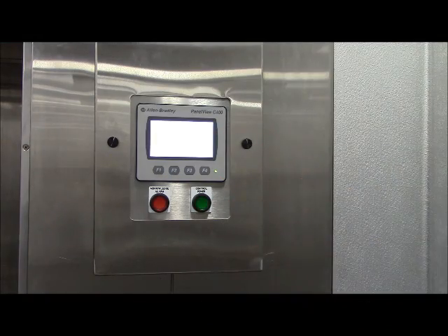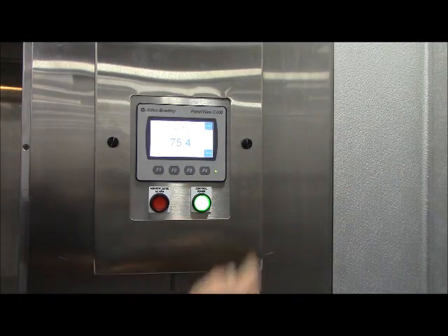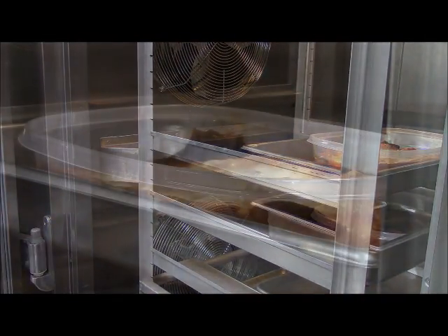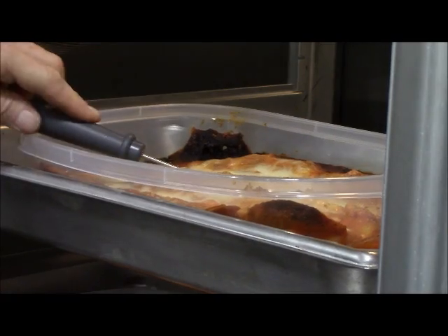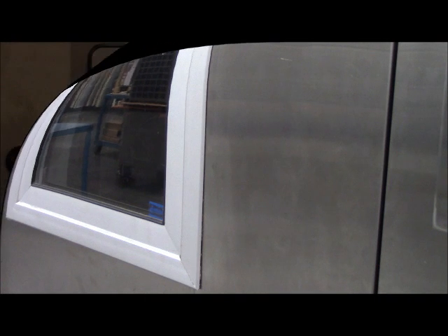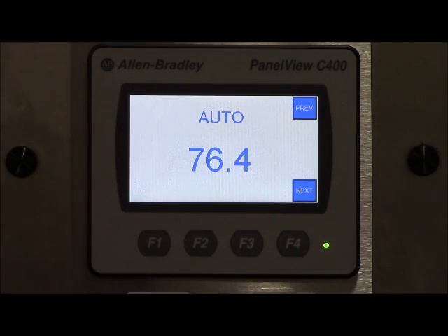The first mode of operation is automatic mode. It is the default mode of operation. The reason is safety. If you've got a probe in the food, you're controlling what's going on in there. And that's automatic mode. Easy and safe. So to use auto mode, turn the unit on. Put the food cart in the blast chiller. Insert at least a product probe in the food and close the door. That's it. You're done. Let's look at the face of the controller while we're in auto mode.